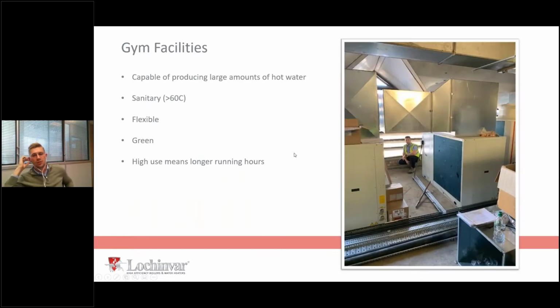Air source heat pumps suit gyms and any high demand hot water application really effectively. I've said previously as well, I work in London and we love heat pumps, but we don't always have outside space. Most heat pumps can be adapted so that you can duct the air outlets and louver the walls, which means the air source heat pump is now working in an indoor environment.